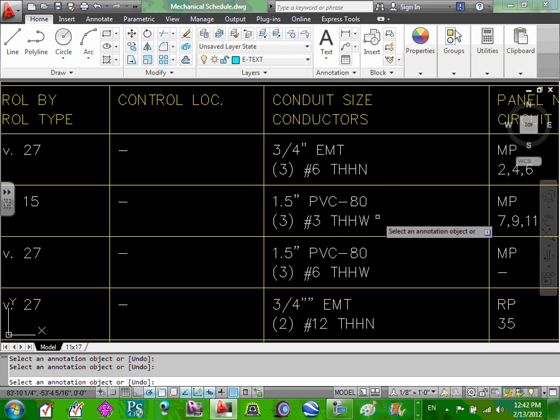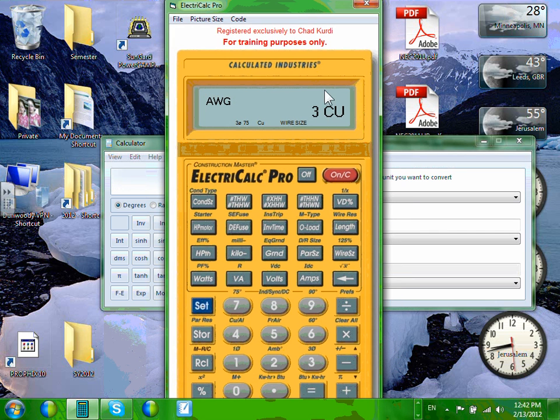Okay, let's see the conduit. I need a conduit. I have 3 conductors because it's only 3-phase, right? I need 3 conductors. So let's clear this one. I have wire size number 3, 3 conductors, THHW, yeah? And I need a conduit size. I have 1 inch EMT, but I don't need EMT, I need PVC schedule 80. Let's use schedule 80. What was the multiplier for schedule 80?